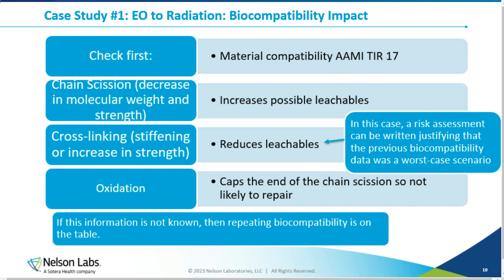All right, so now we're going to look at our biocompatibility considerations when we switch from EO to radiation. I've made this flow chart that we'll go through for each of these case studies. So always check material compatibility first. I put this AAMI TIR document here as a good reference. Of course, there are others, but this is the one that I would go to first. What we want to understand is, when we see that the material is compatible, we still need to understand what's actually happening to the material.